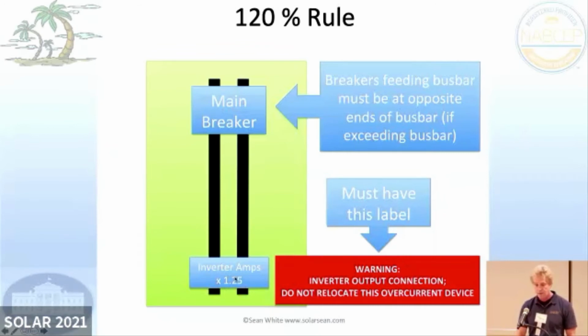And that 20 amps for the solar, or it could be energy storage, is 125% of inverter current. So a 16 amp inverter times 1.25 is 20 amps. So the most we could have is a 16 amp inverter. That's a pretty common thing. 16 amp inverters are more popular.